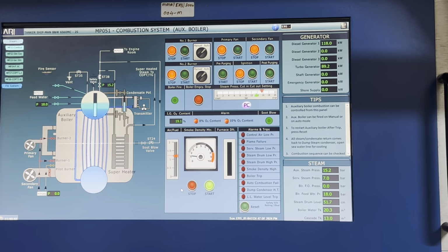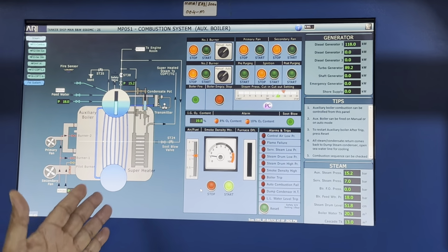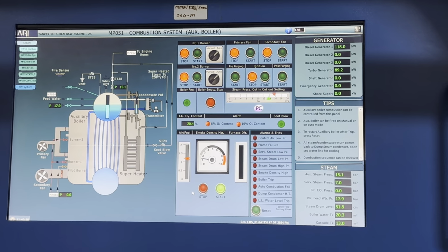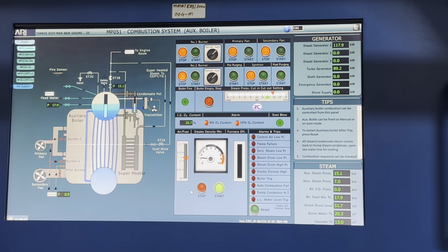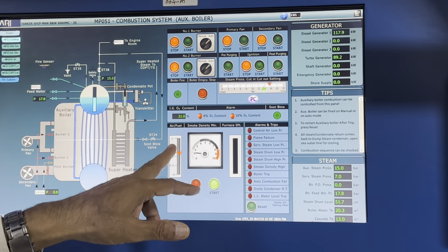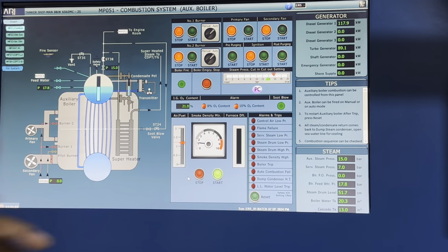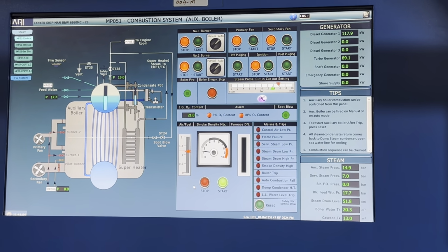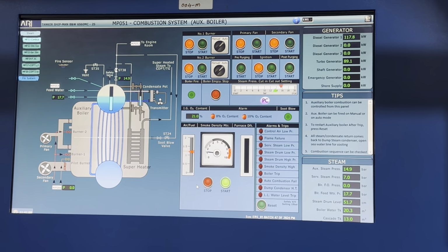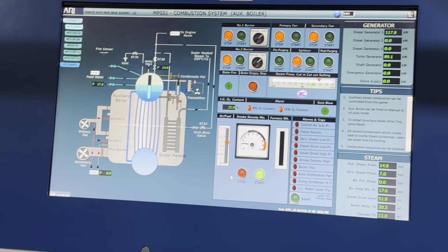That is the stoichiometric ratio. But when you supply the minimum air, because the flue gases have to go out, so in actual running, how much do we make it? We supply extra air, 20 to 30%. So now you can see here, this is 1.5, this is 1. Now 1 you understand is stoichiometric. 1.25 you are supplying here. Correct? So what can we do? Reduce the air ratio. Yes. Can you do or not? Yes, we can do it in order to reduce the oxygen here.